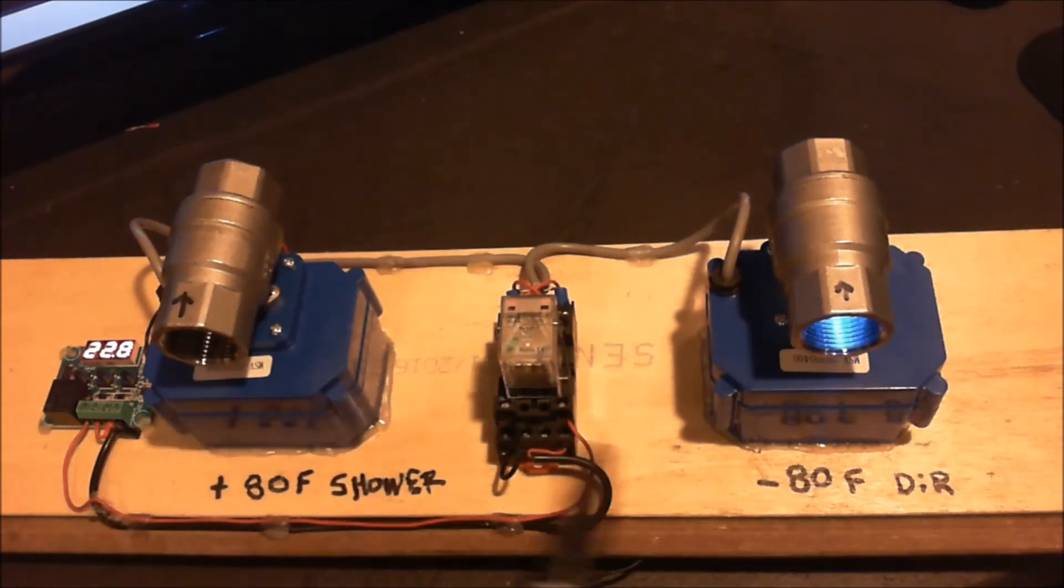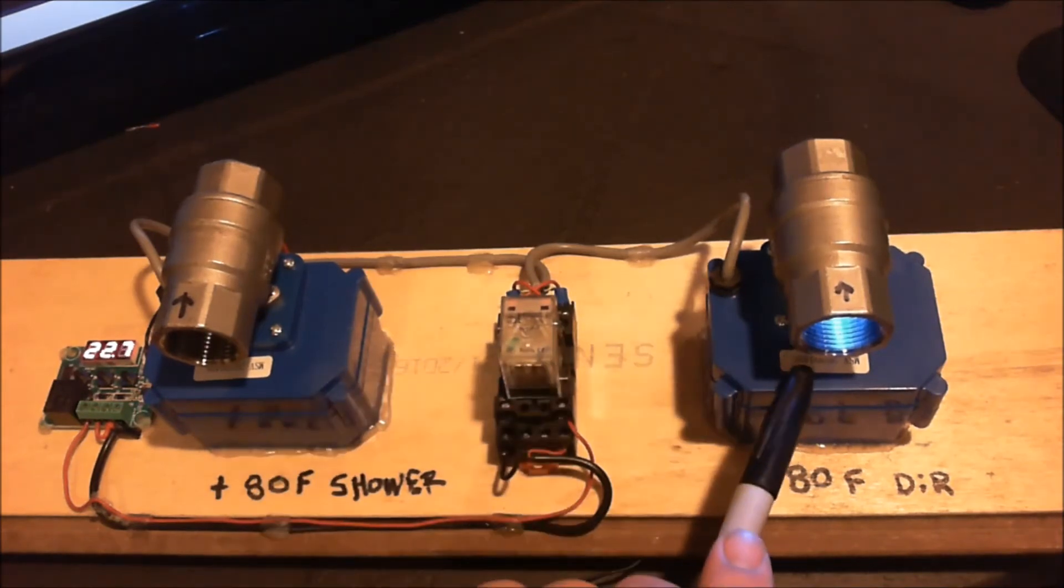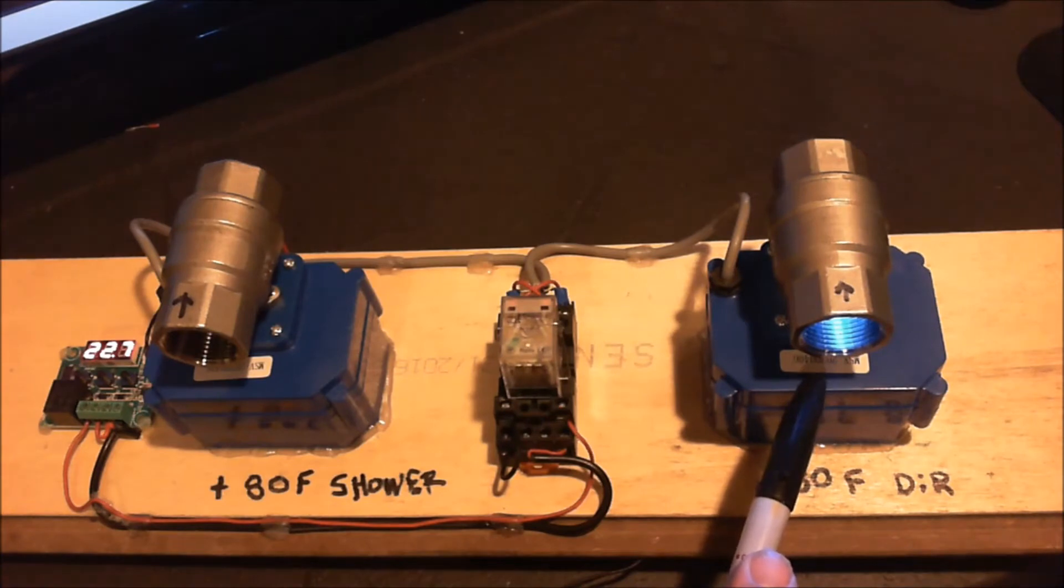Alright, so these valves are motorized. They're either powered open or powered shut. There is no spring return. Energy has to be applied to the valve. It's polarity-reversible. So if you reverse the negative and the positive, the positive and the negative will determine whether or not the valve is being powered open or powered shut.